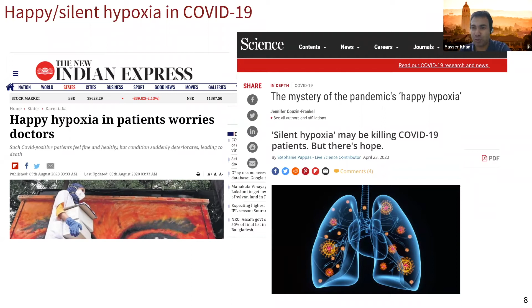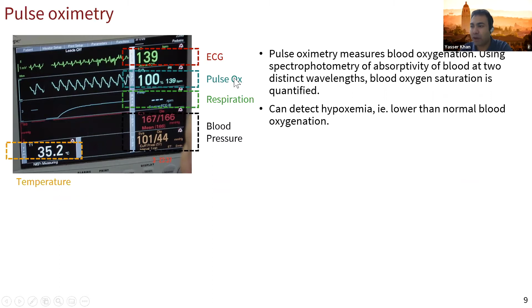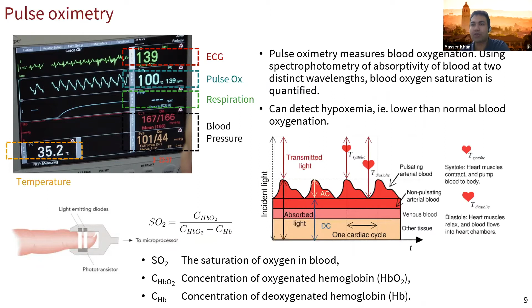So what is pulse oximetry? It's a really standard method of measuring blood oxygen saturation. If you see the monitors in hospitals, they usually have pulse ox information. The measurement is an optical measurement where you have two different lights. They shine through the finger, and then with the sensor, you detect the changes in light. When the heart pumps blood and then retracts blood, it creates this pulsatile waveform. If we use two different colors, we can create a ratiometric measurement. Blood oxygen absorption in different ranges of color, let's say red and near infrared, is quite different. So we can use these two different colors to get a ratiometric measurement of blood oxygenation.